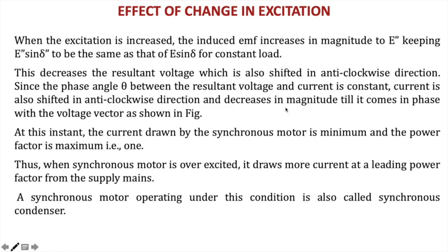So the effect of excitation is that when the synchronous motor is overexcited, it draws more current at a leading power factor from the supply mains, and a synchronous motor operating under this condition is called a synchronous condenser.